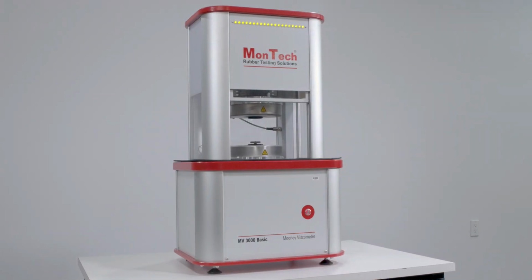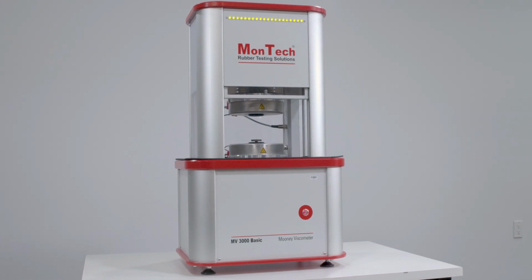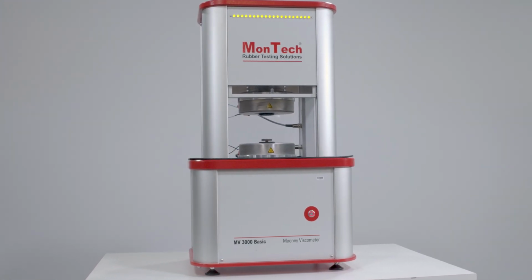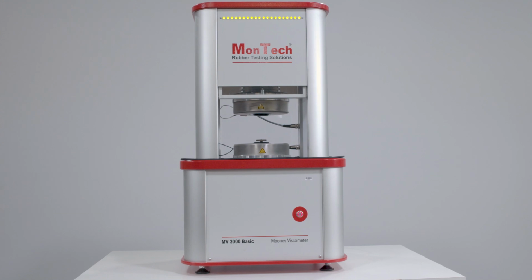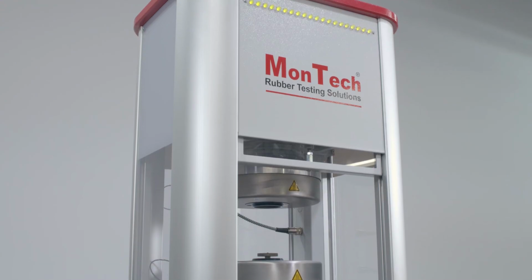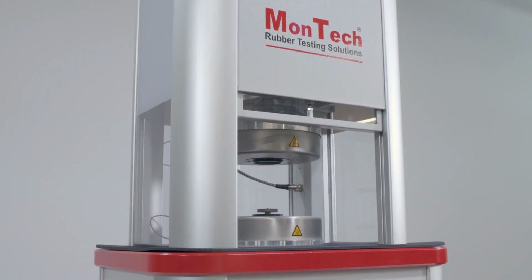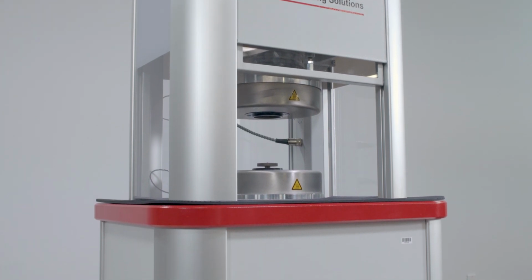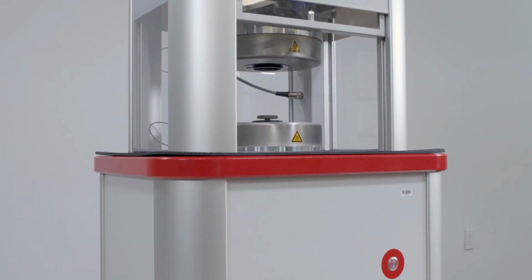The MonTech MV3000 Mooney Viscometer provides the highest levels of precision and repeatability for measuring process viscosity and elasticity of polymers and rubber compounds. It is the perfect value for small laboratories and production control facilities. The MV3000 Basic performs essential tests for quality control and research and development applications.